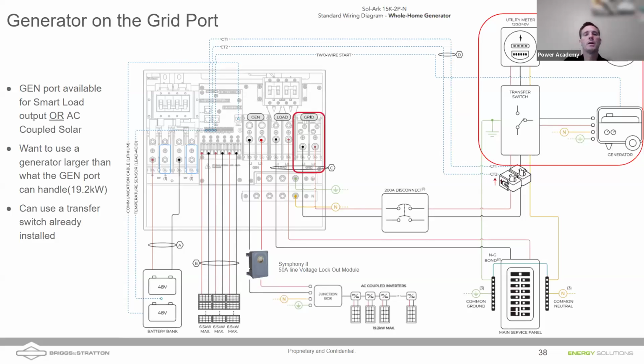The alternator there. Okay, so we can put a lockout module on the AC coupled solar, and that just means anytime the generator's on, we can have the AC coupled solar turn off. And as long as the AC coupled solar is producing excess energy in addition to the loads of the house, the batteries should stay charged up, and the generator is not going to start unless those batteries are at a low value, as long as we program it appropriately anyway.